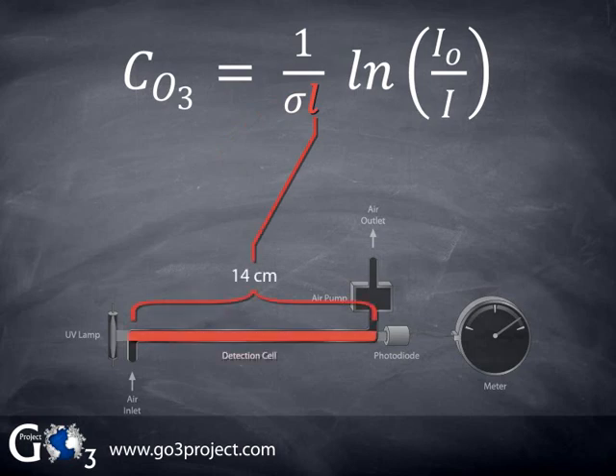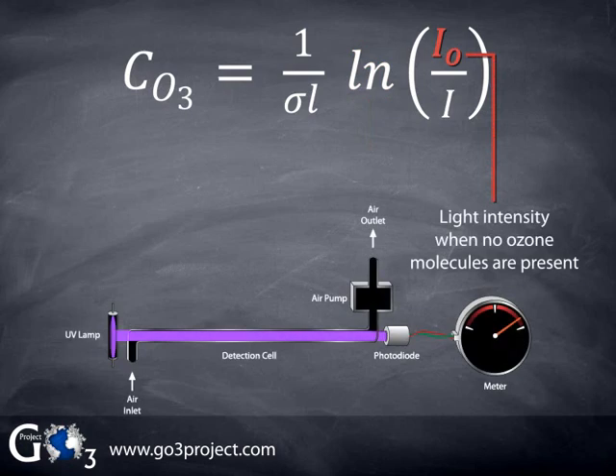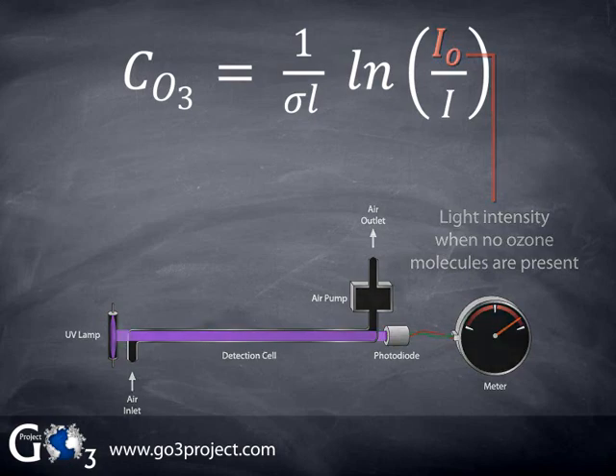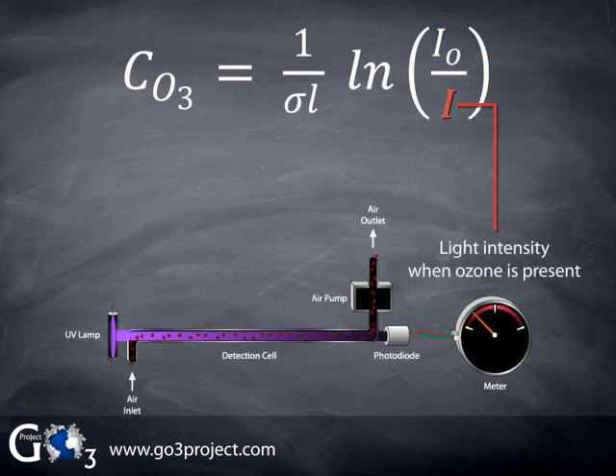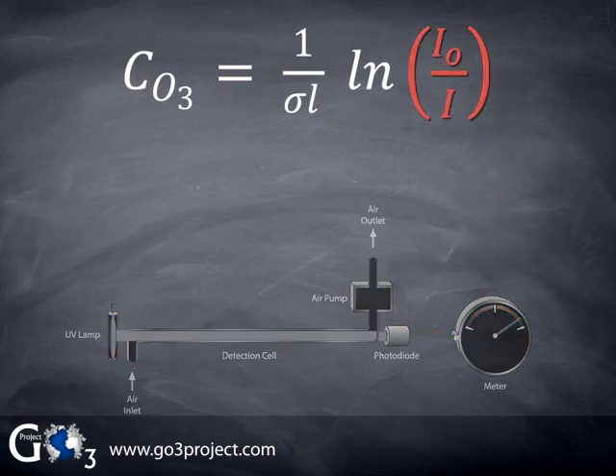L is the length of the detection cell. For the GO3 ozone monitor, L is 14 centimeters, or about 5 1⁄2 inches long. Ln is the natural logarithm, the logarithm to the base E. I0 or I sub-zero is the light intensity when no ozone molecules are present in the detection cell. I is the light intensity when ozone molecules are present. Note that I0 is always larger than I. So the ratio of I0 to I is always greater than 1, so the logarithm will always be positive. After measuring I0 with no ozone in the detection cell and I with ozone present, we can plug the two measured values into the Beer-Lambert law and calculate the ozone concentration.